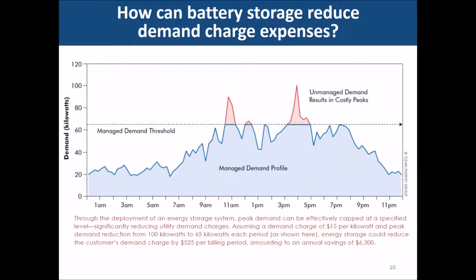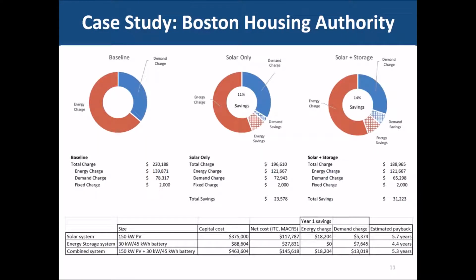The break-even point, a number of studies have shown, for energy storage, particularly lithium-ion batteries, to make sense for this is about $15 per kilowatt in the rate structure that you're under. In this case, if you were able to do this every month, that would add up to about $6,000 in annual savings. So I want to look at a couple of real-world case studies for how these economics play out.